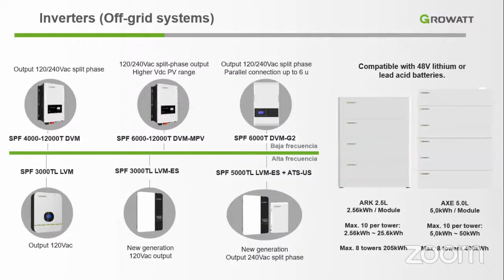So what is an off-grid system in Growatt? The inverter has to be connected to modules, batteries, utility, or generator, depending on you. All of this is to supply the AC load. Take into account that while we can connect it to the utility, we are not going to inject energy into the grid. This is only for consumption.